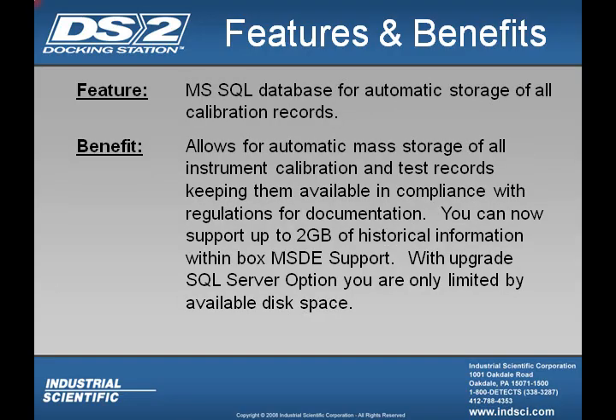Now your docking station will use an MS SQL database for automatic storage of all your calibration records. The benefit of this is, of course, allowing for automated mass storage of all instrument calibration and test records, keeping them available in compliance with regulation for documentation. It can now support up to 2 gigabytes of historical information with the in-box MSDE support. With the upgrade SQL Server option, you are only limited by the available disk space.